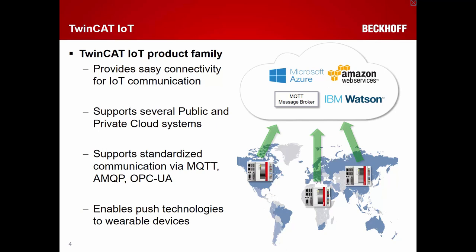TwinCat IoT is all about standardized communication, meaning you can use protocols like MQTT, AMQP, and OPC UA to establish connectivity to cloud services. TwinCat IoT also has its own smartphone app, enabling push notifications to wearable devices. You can use function blocks within your PLC logic to send alarms to wearable devices.